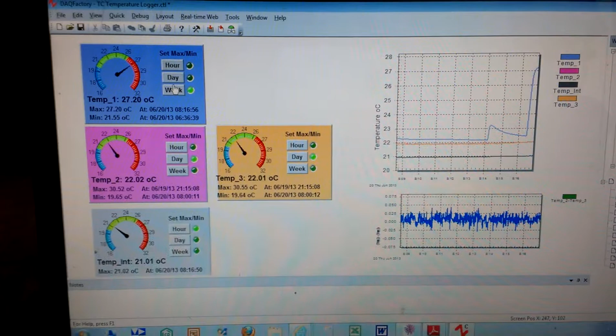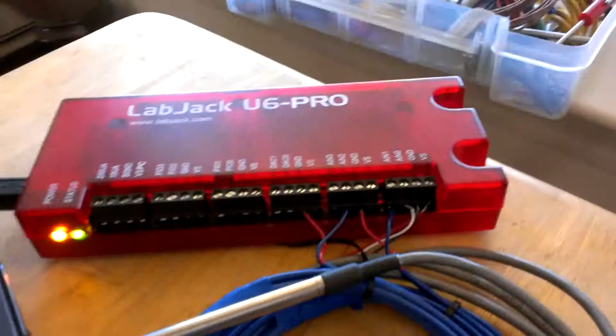Now it's a little trickier to measure a thermocouple because the voltage output of a thermocouple is the difference between the sensing tip and the cold junction voltage. So you need to know the cold junction temperature, the temperature of the ends of these wires where the thermocouples terminate. The whole wire is actually part of the thermocouple circuit, and where it terminates is the cold junction temperature. Right now I'm using the internal temperature sensor built into the LabJack, and that's displayed here as the cold junction temperature. When I build my real product, I'm going to use an LM34CAZ that's actually fused to a real cold junction, and use that for cold junction calibration.